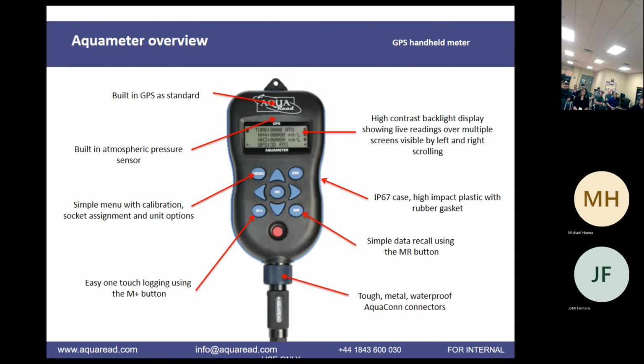We do averaging as well on the data. For things like chlorophyll, if you had window or snap sampling, where the sensor is on for so long then stops, on then stops, that causes spiky data. That's why manufacturers use averaging, so you can pull out zeros or high trends in low flow sampling with groundwater, because you're not interested in spikes, you're interested in what the data is actually doing over a period of time. With our optical sensors, especially on the Pro series, those sensors stay on for quite a while and give a nice running average of information, as opposed to being spiky.